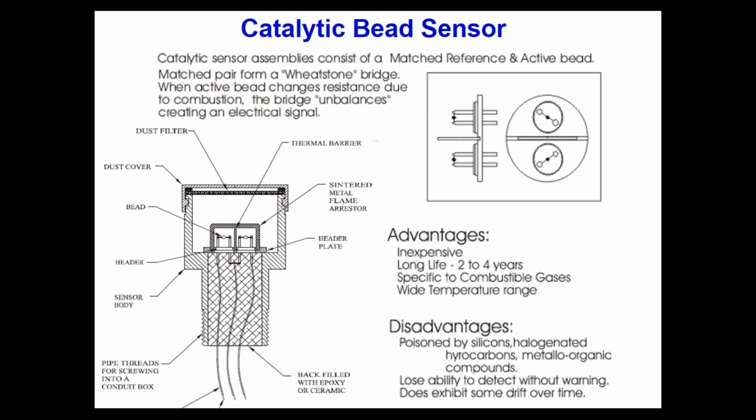We have used catalytic bead in an environment that had air conditioning systems, halon dumps, for example. If you use a catalytic bead in a room that's monitoring for some combustible gas, and you have a halon system that dumps in case of a low alarm or high alarm, one of the problems is that the halon dump will also kill the catalytic bead. So you probably have to replace the bead after the alarm goes off.